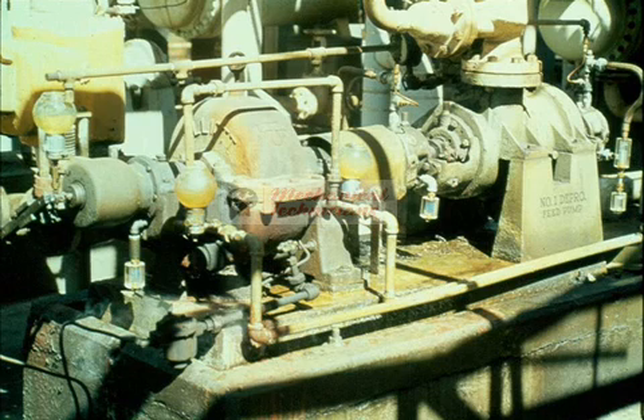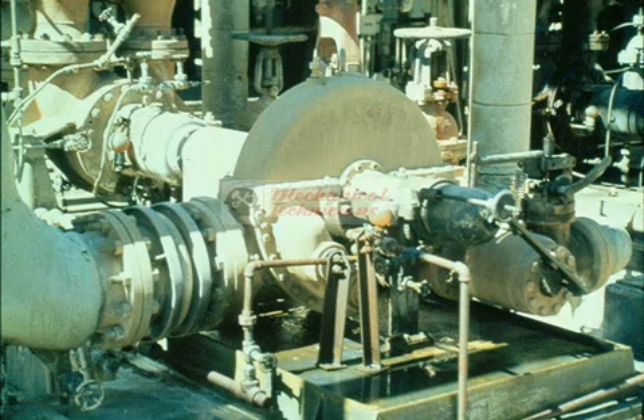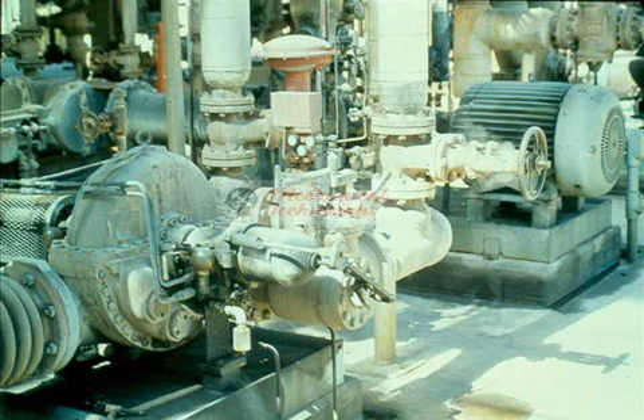Typical uses of these smaller turbines would be to drive lubricating and seal oil pumps, chemical feed pumps, and medium-sized process and water pumps. Medium-sized turbines from 100 to 500 horsepower are generally used to drive larger product pumps, fans, blowers, and cooling water pumps.